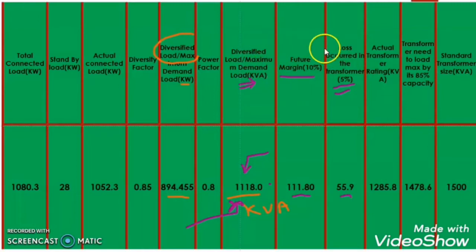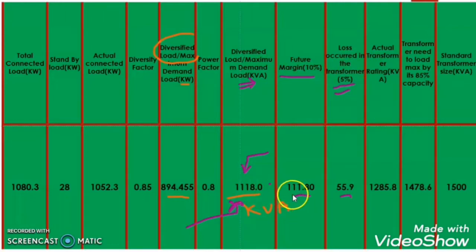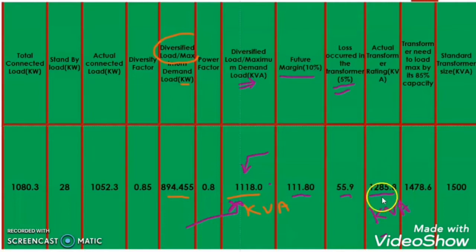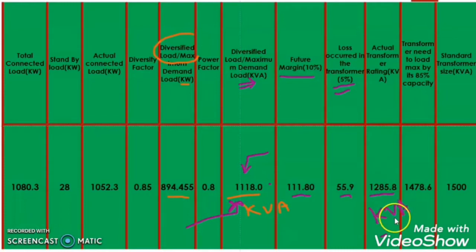Now, what is the actual load on the transformer considering the future margin and the loss margin? This will be diversified load in kVA plus the future margin plus the transformer losses. So it will be 1118 plus 111.8 plus 55.9, giving an actual load on the transformer of 1285.8 kVA. If we select a transformer of exactly 1285.8 kVA, it would have to run at 100% capacity all the time, which is not recommended for electrical equipment.